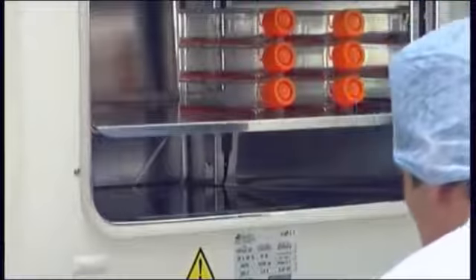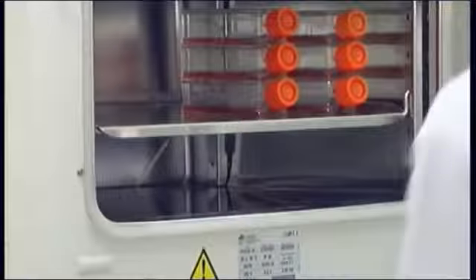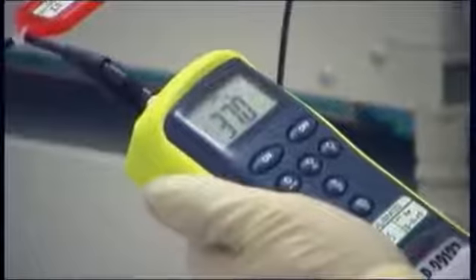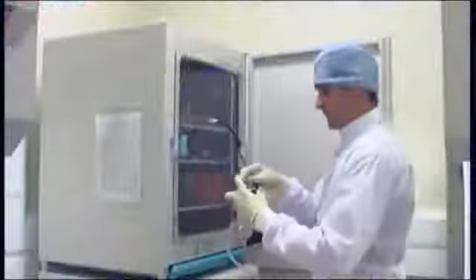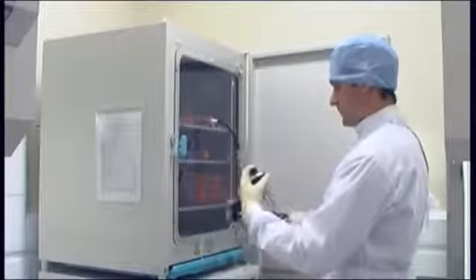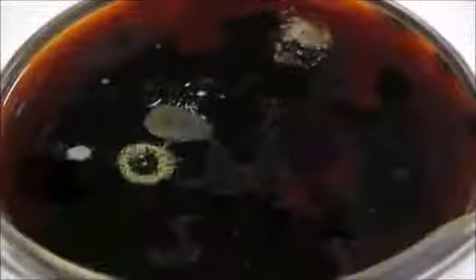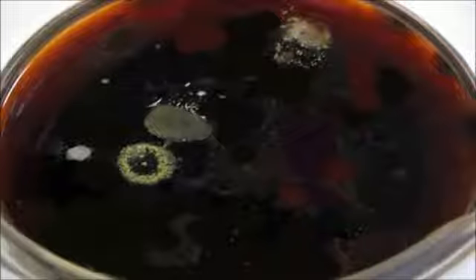Regularly check and replace water in the reservoir. Independently check the temperature using a calibrated thermometer and CO2 levels using a Fyrite gas analyzer or similar. Regularly check CO2 supply cylinder levels are sufficient, especially before weekends and holidays. Incubators are ideal breeding grounds for bacteria and molds, which could contaminate your cultures. Minimize this risk with regular monitoring and cleaning.